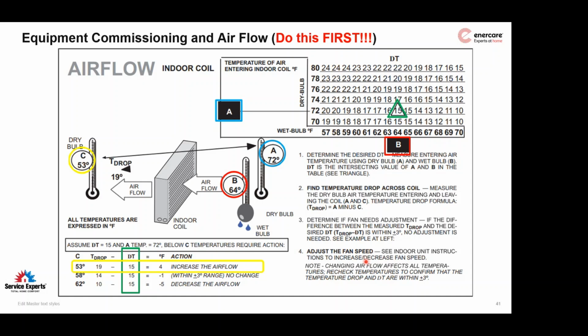Basically what's happening is the air, as it passes over the coil, has too much time in contact with the refrigerant and you're getting too much temperature difference. You probably don't have enough airflow. You can speed it up. Say, taking the same readings, you end up with 58 degrees, which gives you basically a 14-degree TD. That's much closer to the expected 15. Perfect. Airflow is set up correctly, you're getting the appropriate temperature difference across the coil, and there's a good chance your refrigerant is charged correctly. Confirm with superheat or subcooling, depending on what orifice or TX valve you're using.